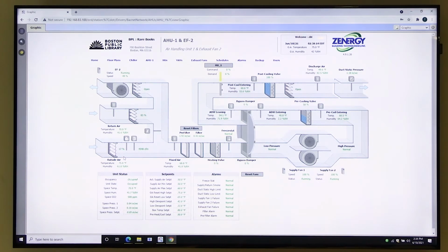So it's being mapped from the global system, the graphics. It's actually wired to the chiller controller, so that is outside, yes, on the roof, and then it's being mapped to this device that's controlling the air handler. So it's going to match exactly. But shouldn't it? It's 20% higher. That's a really good question.